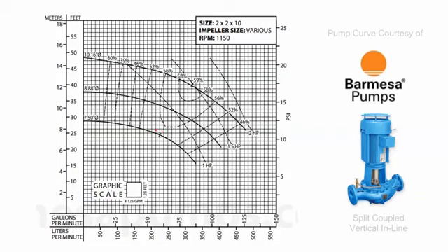Now, the rule of thumb is, of course, that when you're sizing a pump, you want efficient operation, because these pumps are, in most cases, somewhat balanced for that efficient operation. Operating too far to the right-hand side of the curve can cause premature failure of the motor and extra wear and tear. Operating too far to the left-hand side of the curve can become extremely inefficient and cause you to waste a lot of excess money on energy costs, as well as damage the pump through imbalanced operation. So it's always recommended that when you're sizing or selecting a pump, that you tend to try to operate within its most efficient range, or you target that most efficient range.